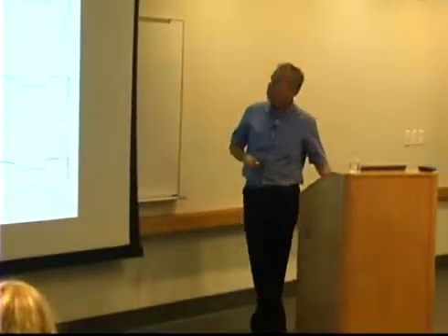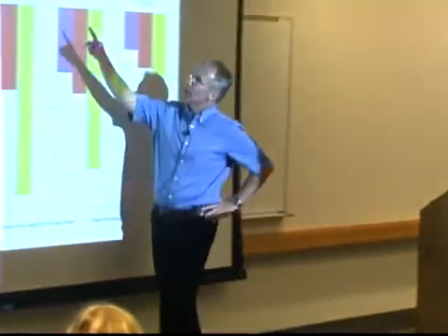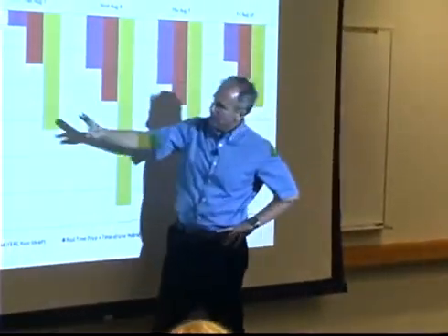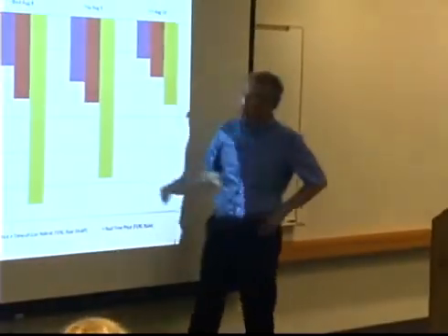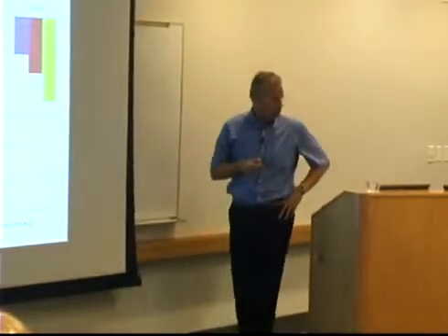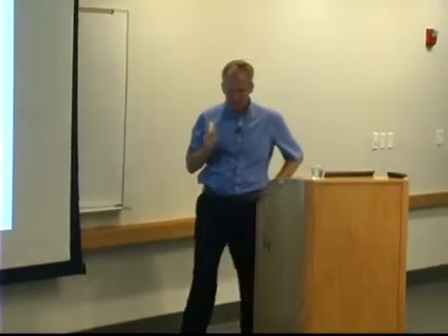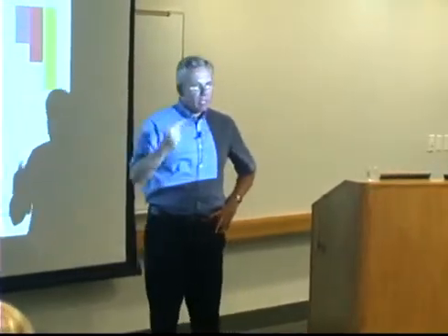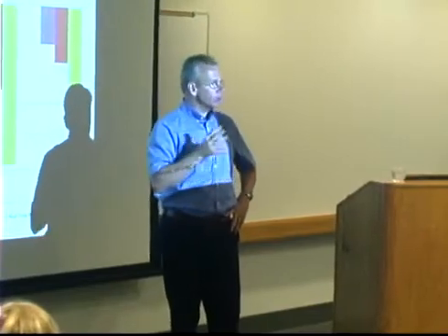It turns out that it's better every time. If you take that 4 a.m. pre-cooling heuristic, depending on the day of the week for a particular pricing strategy, you can outperform that simple heuristic every day. It's just the degree of outperforming it is different. So this basically tells us that with online MPC, we can control a building in a way that responds to the current weather conditions and the current grid constraints and grid pricing conditions.